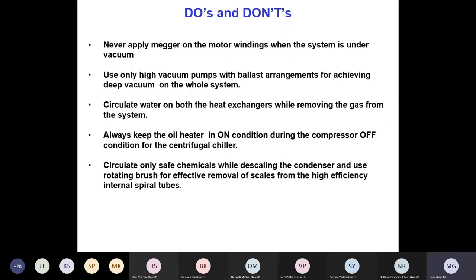Never apply a megger on the motor winding when the system is under vacuum. It can lead to failure of the motor winding. Use only a high vacuum pump, or a two-stage pump if it has a ballast. Always use that, because generally all the manufacturers recommend a minimum of 500 micron vacuum to keep all the moisture out of the system so the compressor works clean. But if you use a single vacuum pump, its power is limited and it cannot pull down to 500. Naturally you will stay at around 2000 micron, so some condensation and non-condensables will always remain there. So please use proper vacuum pumps.